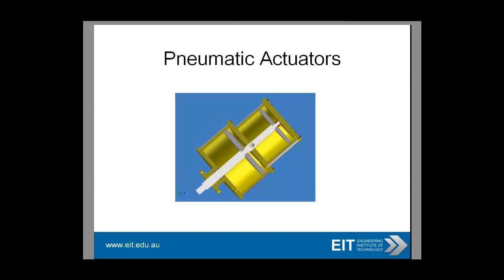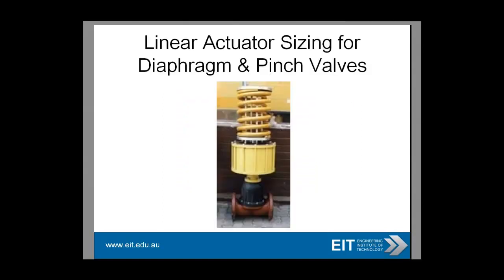Disadvantages would be that pneumatic actuators always require a clean source of air. Sometimes you want a hand wheel override, which can be expensive. Generally, pneumatic actuators — pneumatic meaning they work with air — are going to be large, bulky, and extremely heavy. All of the force needed must overcome the force of that spring — the fail-safe action, that spring return. Remember the potential energy that I spoke about last week, giving you an idea of the potential energy that is going to kick in.